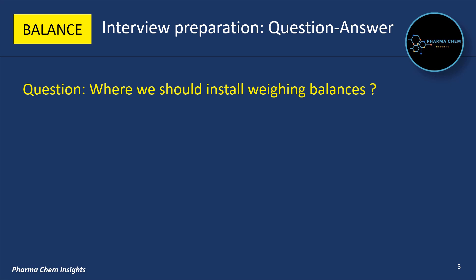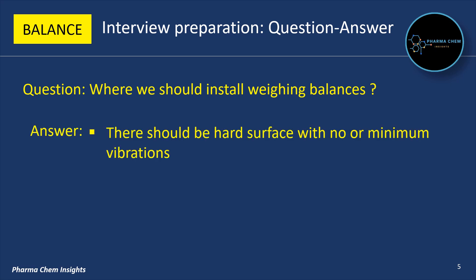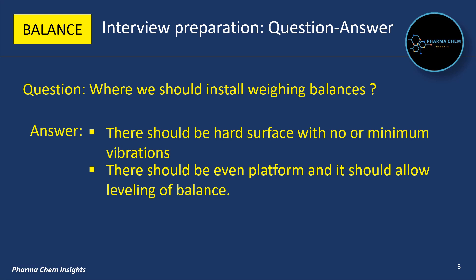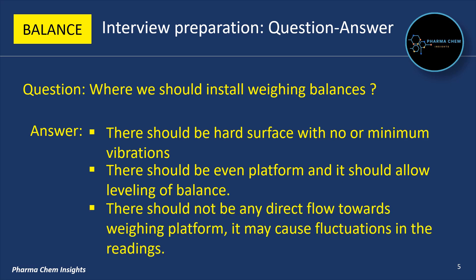Next question: where should we install weighing balances? The following points should be considered while installing weighing balances. First, there should be a hard surface with no or minimum vibrations. Second, there should be an even platform that allows leveling of the balance. Third, there should not be any direct airflow towards the weighing platform, as it may cause fluctuations in the readings.